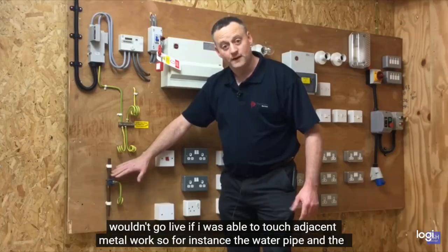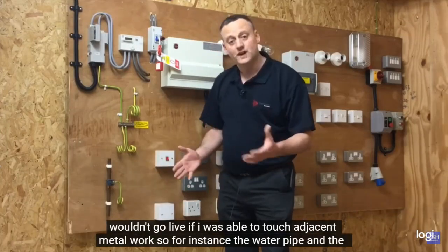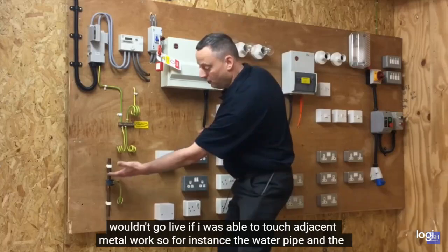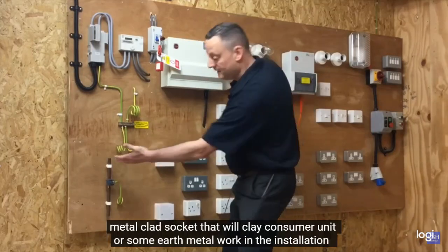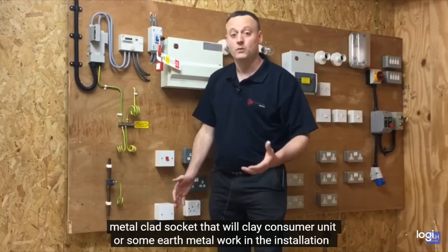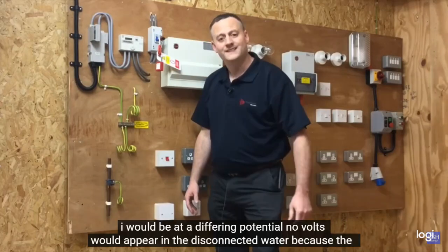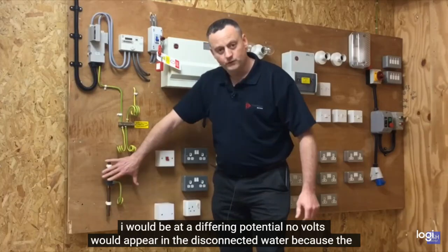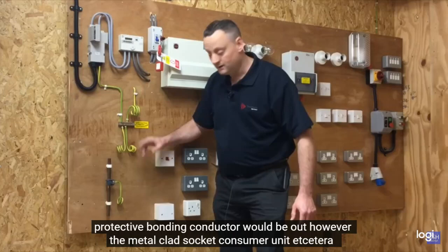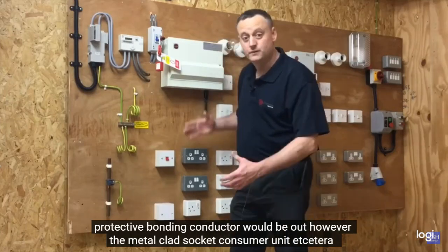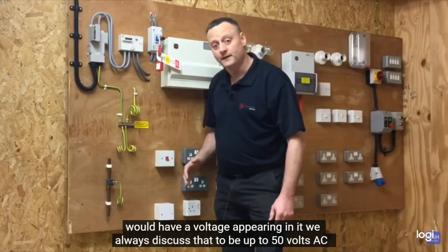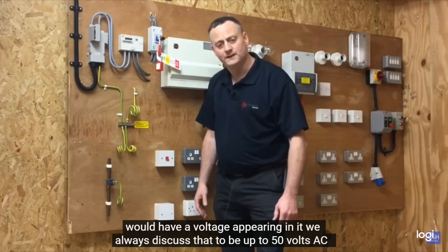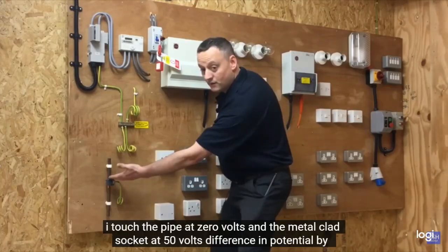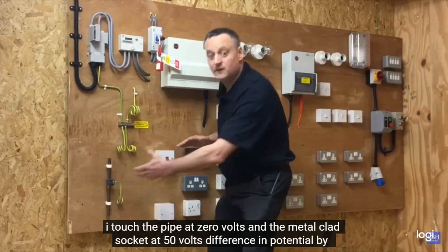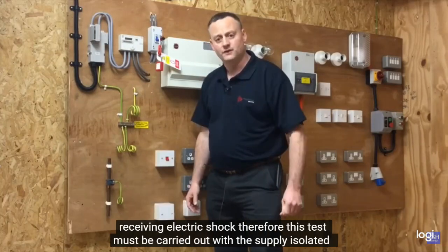go live. If I was able to touch adjacent metalwork, so for instance the water pipe and the metal clad socket, metal clad consumer unit, or some earthed metalwork in the installation, I would be at a differing potential. No volts would appear in the disconnected water pipe because the protective bonding conductor would be out. However, the metal clad socket, consumer unit, etc., would have a voltage appearing in it. We always discuss that to be up to 50 volts AC. I touch the pipe at 0 volts and the metal clad socket at 50 volts. Difference in potential, I receive an electric shock.